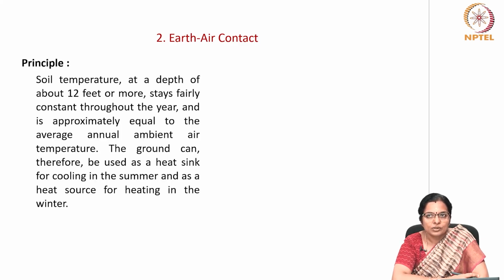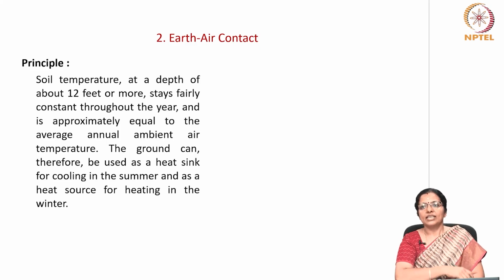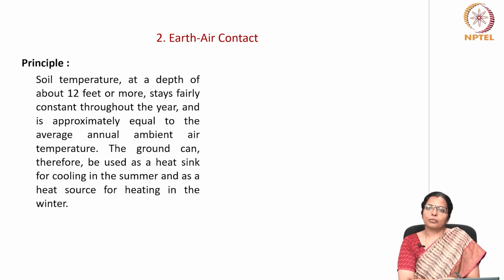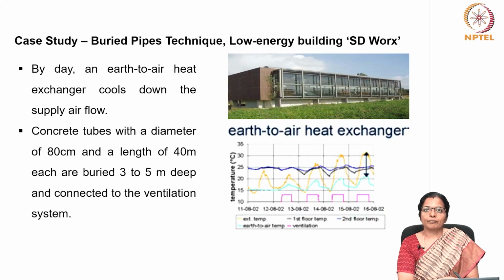The second principle that is used in this building is the earth-air contact, which works on the principle that the soil temperature at a depth of about 12 feet or more stays fairly constant throughout the year and is approximately equal to the average annual ambient air temperature. The ground can therefore be used as a heat sink for cooling in the summer and as a heat source for heating in the winter. In this case, during the day, a earth to air heat exchanger cools down the supply airflow. Concrete tubes with a diameter of 80 centimeter and length of 40 meters each are buried 3 to 5 meters deep and connected to the ventilation system.